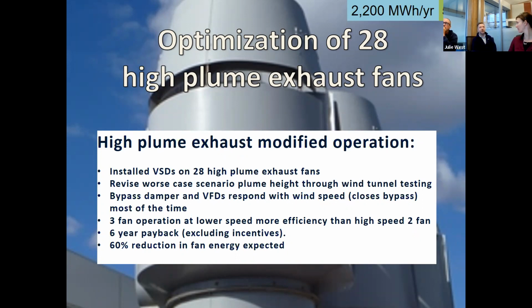On the subsequent buildings we got away from that and mainly just went to the lowest best case scenario, just for maintenance. There were 2 different versions of the project. One was called simple turn down, where the energy savings compared to the extra cost of having them modulate and doing the further wind tunnel testing and mapping didn't have a payback. So we went away from the anemometers on buildings that were not going to benefit from it. We went to what's called a simple turn down, where it isn't the lowest possible, but there wasn't enough left on the table for us to spend the extra money to go down further.